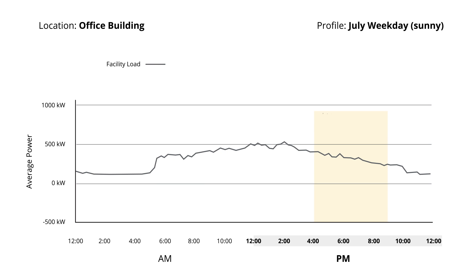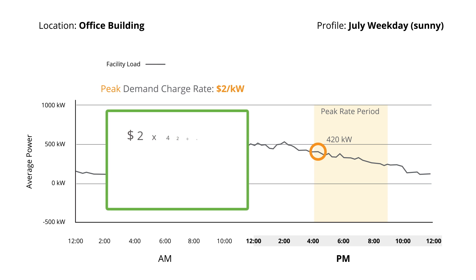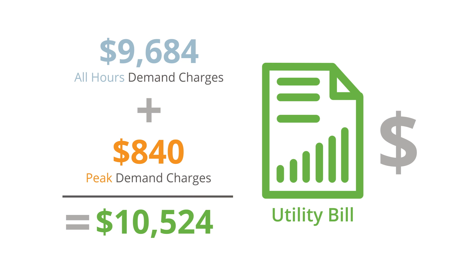But there's a time of use factor here as well. The peak period for this particular utility rate structure is from 4 p.m. to 9 p.m. in the evening, and the highest average power usage within that timeframe occurs around 4:30 p.m. and is 420 kilowatts. With a peak demand charge rate of $2 per kilowatt, peak demand charges amount to an additional $840 per billing cycle. So the total demand charges would equal $10,524 in the month of July.